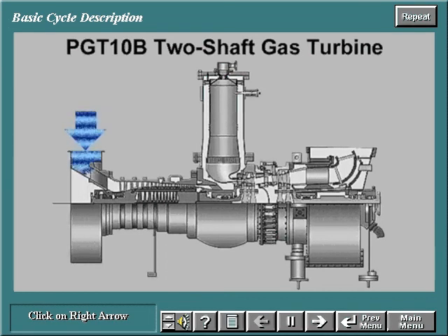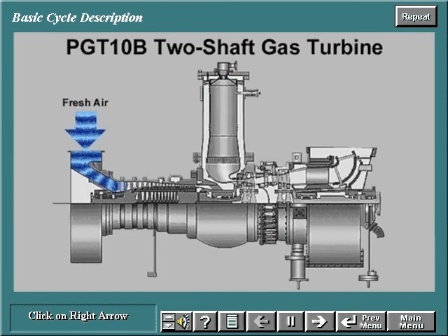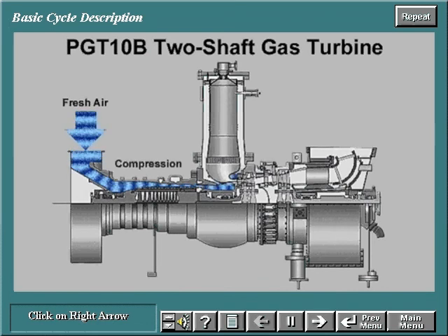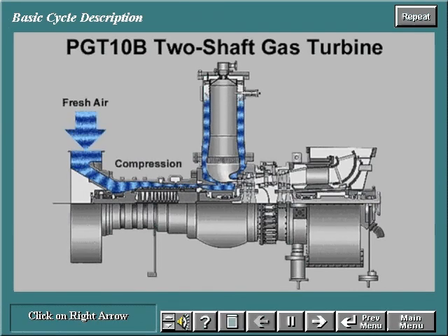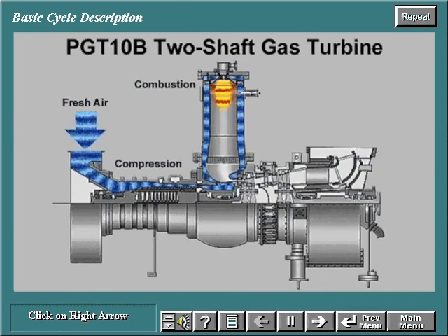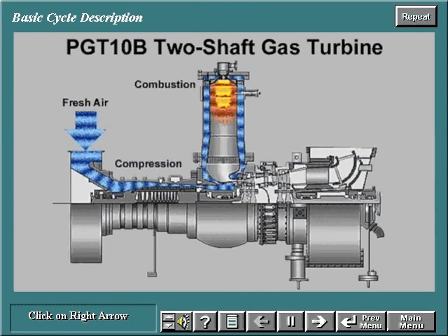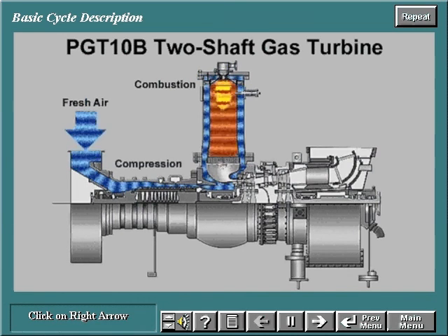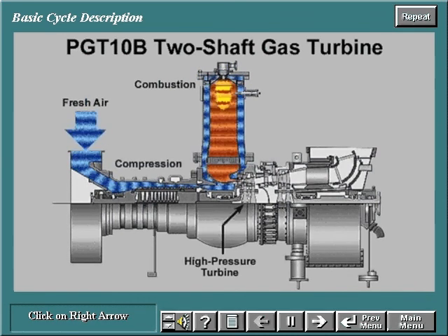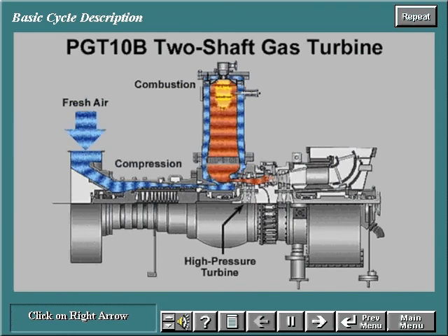A two-shaft gas turbine draws in fresh air and compresses it to a higher pressure by means of an axial flow compressor. The compressed air is mixed with fuel in the combustion chamber and burned, increasing the energy level. The resulting hot gas is then expanded through the high-pressure turbine where some of the gas energy is converted into mechanical energy that drives the compressor.